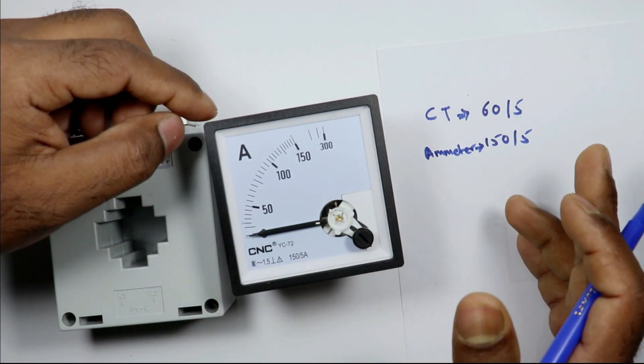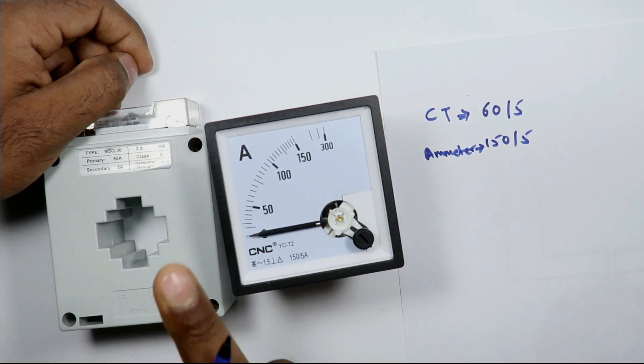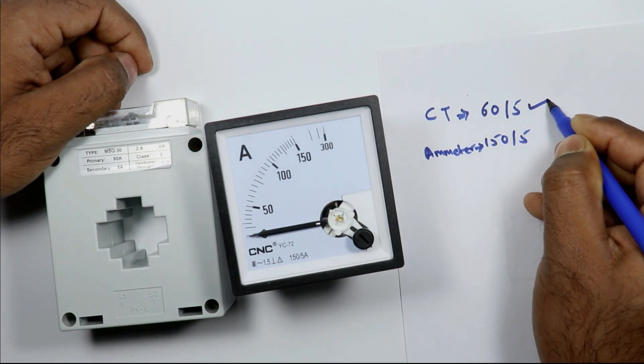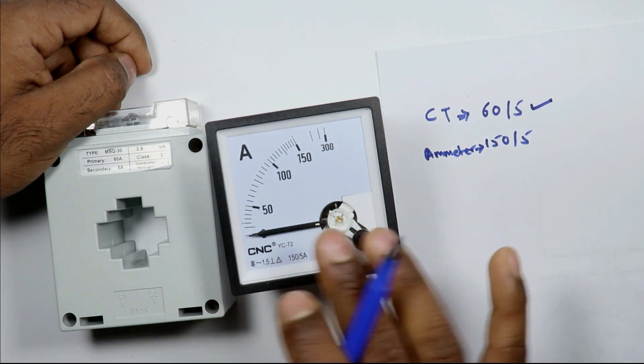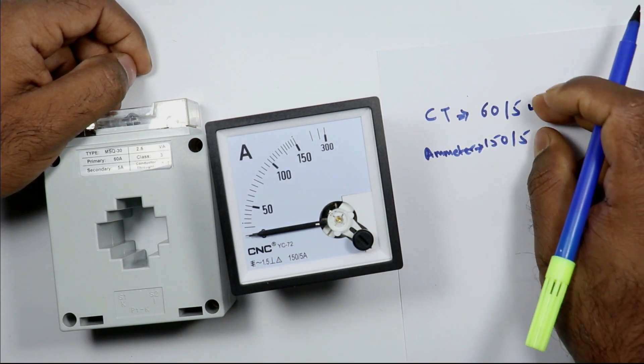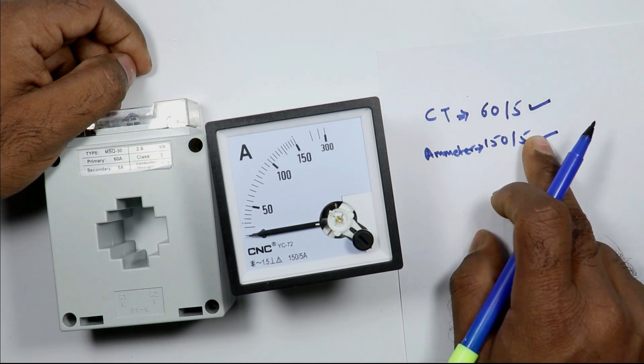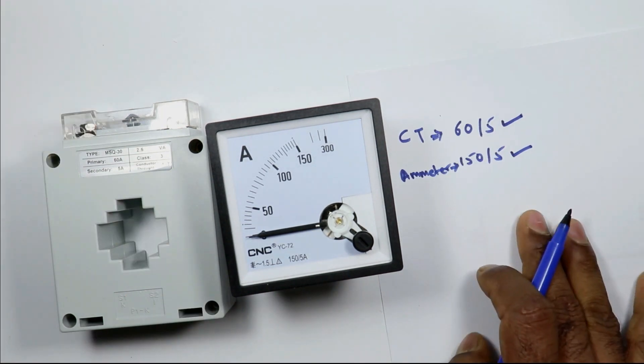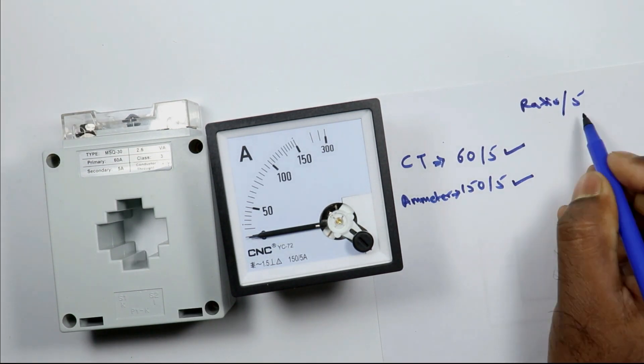Keep one thing in mind before scaling: the ratio of this CT in output is 5 and also secondary ratio of ammeter is 5. This means secondary must be same. You will find two types of ratio for CT. Ratio can be 5 or can be 1.